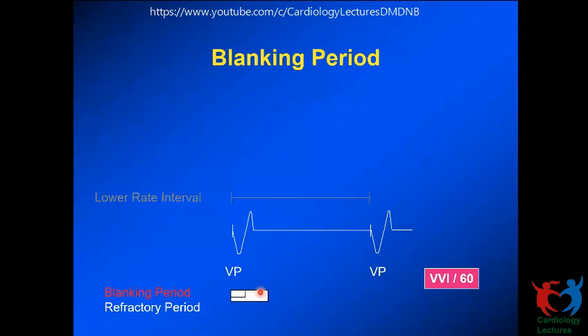Then after that, it's the refractory period where the pacemaker will sense it, but it will call it a refractory sense. It will not reset the clock if there is a sensing here. And in the current pacemakers, the blanking period in the same chamber, the ventricle, is not programmable. It's an automatically adjusting one. It will automatically vary between 50 and 100 milliseconds, and you could program the refractory period to something like 300 milliseconds, and in a typical dual chamber pacemaker, it's about 250 milliseconds. So the first portion is totally blanked, and then the next portion is the refractory one, where it will sense and it will not reset the clock. In other words, it will ignore that event.